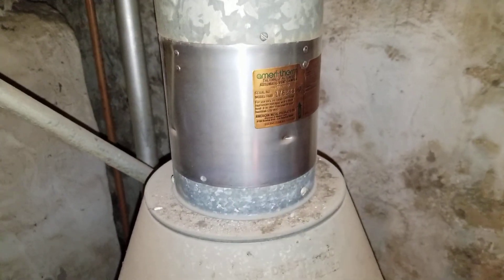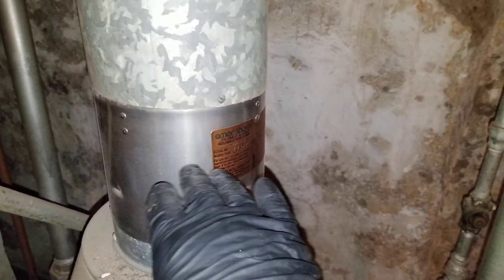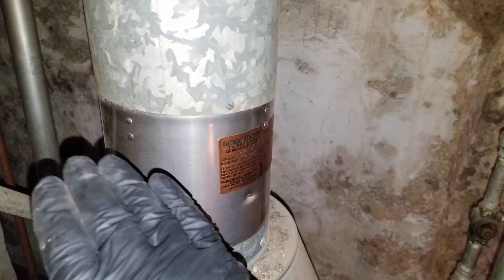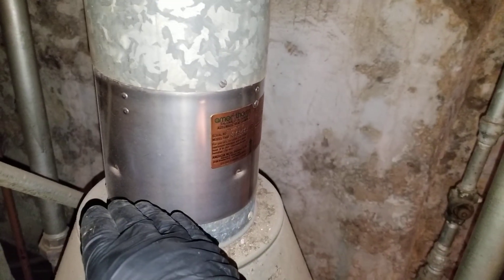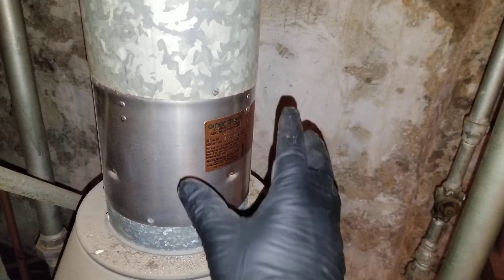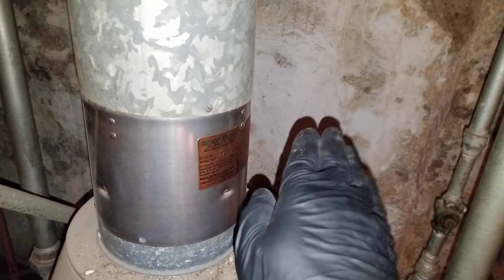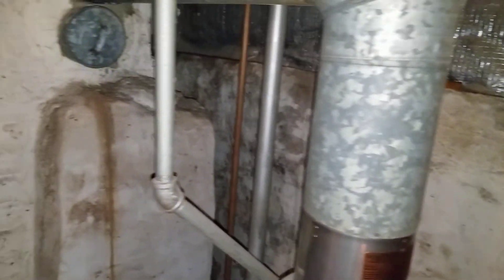Here is a draft hood — this is a natural draft boiler. The brand name is Ameri-Therm. Inside, it's basically almost closed. There are bimetal shutters — when the boiler is not running and cools down, they close. When the boiler comes on, they warm up and open. There are four of them opening in different directions to allow the draft to be created and fumes to go out.